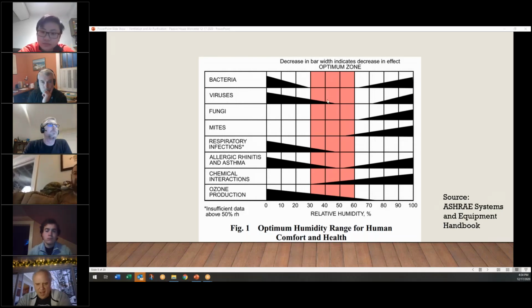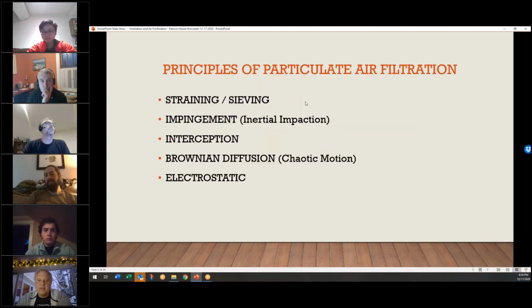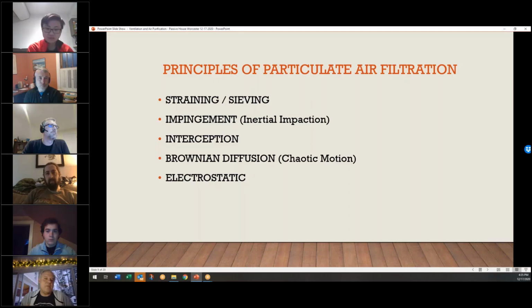So that's that aspect. And if we go to the next page, I forget what I had on the next slide. Okay, so now we get into filtration, right? Particulate filters. How do filters work? Air filters, that's what we're talking about. It's kind of like a strainer. If you make the filter media tight enough, any particle that's too big won't fit through. Basically, it's going to get stuck in the mat, and that's how it's blocked.